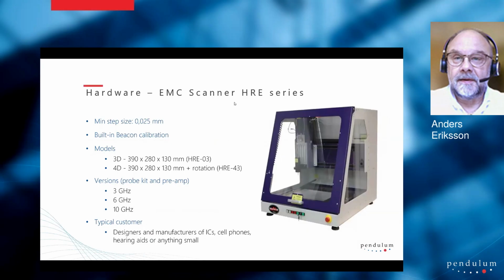The high resolution scanners, like I said, has 25 microns step size. It has a built-in beacon calibration at the back of the scanner table around here. And the measuring cube is 39 by 28 by 13 centimeters. It comes in 3-dimensional or 4-dimensional, where the 4th dimension is rotating the probe around its own axis. It comes with the same probe kit options and preamp, and like I said, this is mainly for companies producing very, very small things.